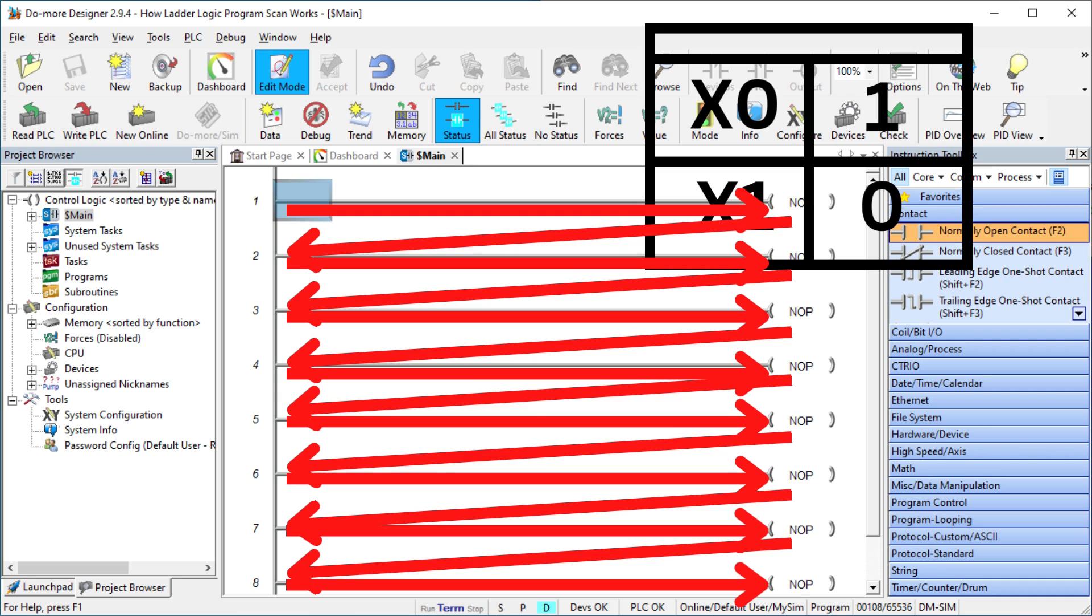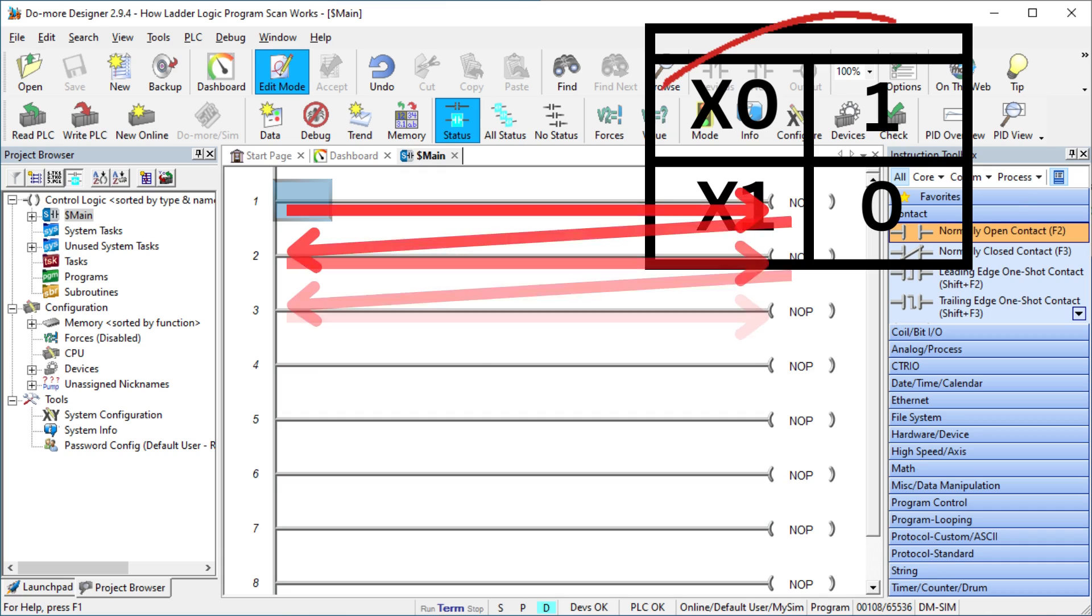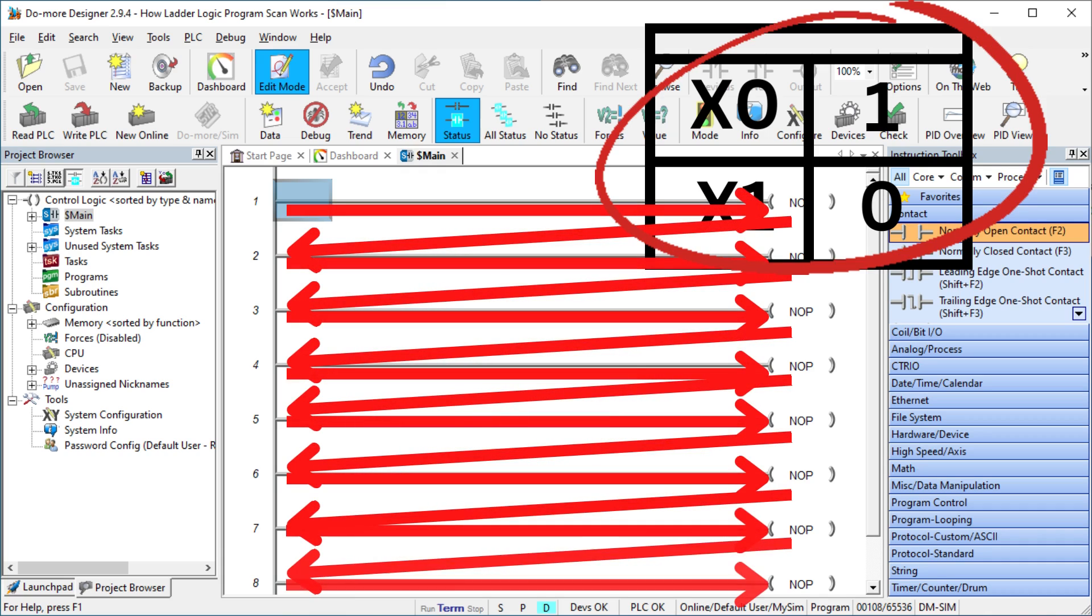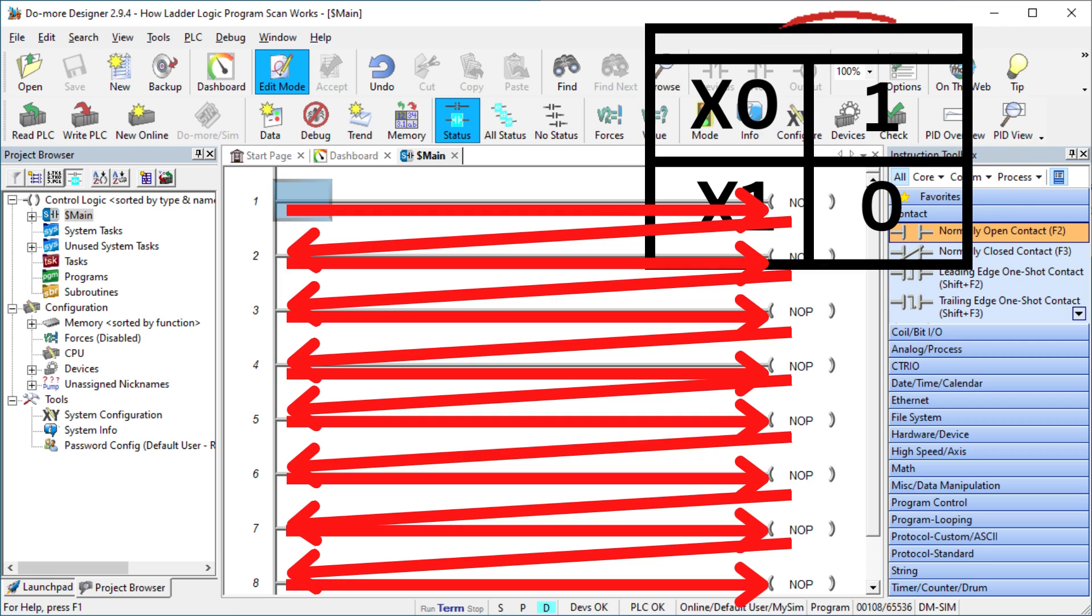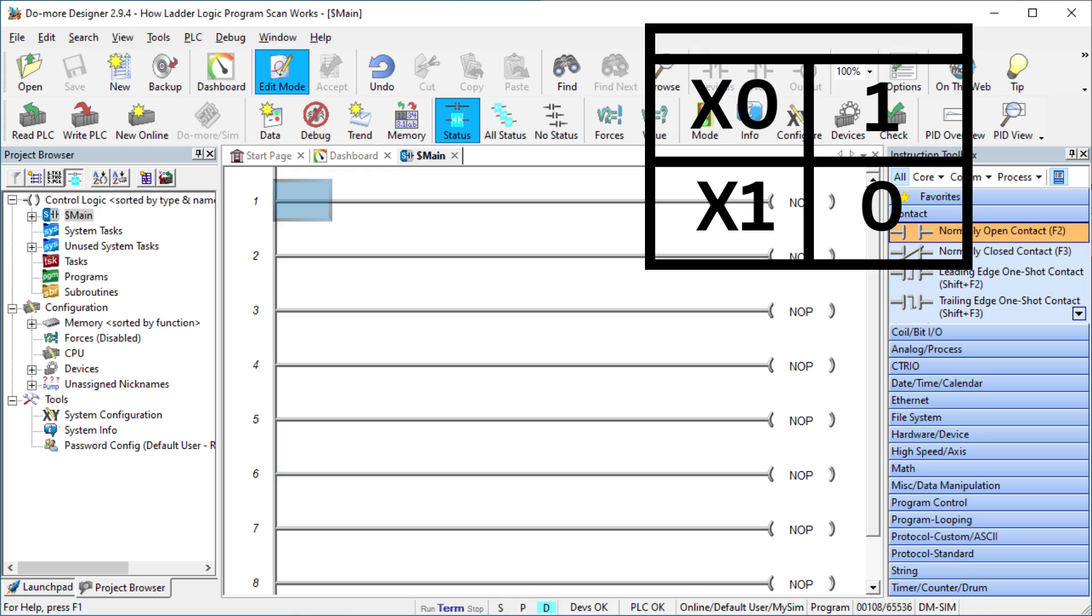The outputs from the previous rung are available for the next rung to use. This means that the memory table is updated as each rung of ladder logic is solved and the next rung will be able to use this modified information in the table. Let's look at an example.